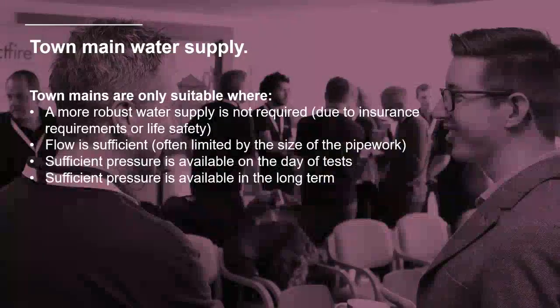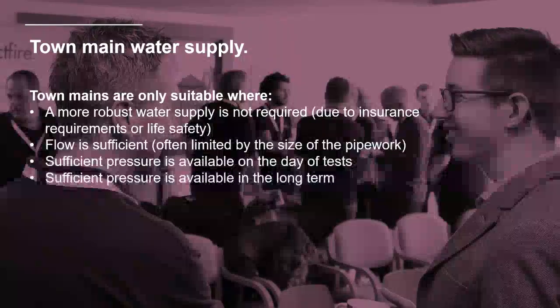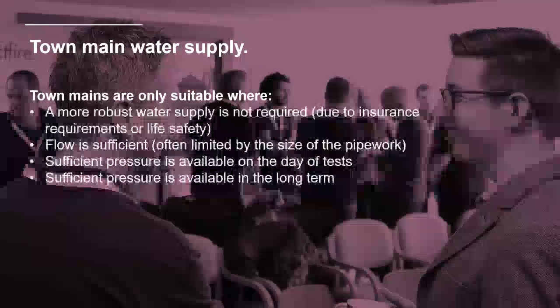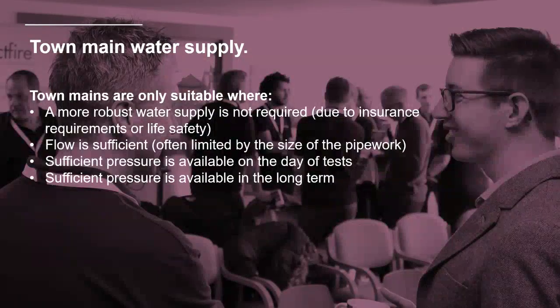Town main supplies are only suitable where a more robust water supply is not required due to insurance requirements or life safety. Again, in previous presentations, I've talked specifically about life safety. Remember, where we need at least a superior twin water supply, a town main doesn't meet that requirement. And with insurance, they might say we need a grade 1 water supply, or we might need a grade 2 water supply. As I've already mentioned, the town main is only grade 3 and therefore wouldn't meet that criteria. So there are going to be instances where, due to other factors, they're looking for a more robust water supply, a superior supply, a duplicate supply, superior twin, something else other than the town main.